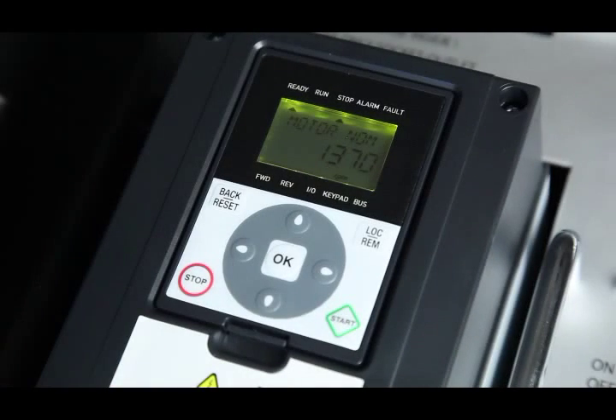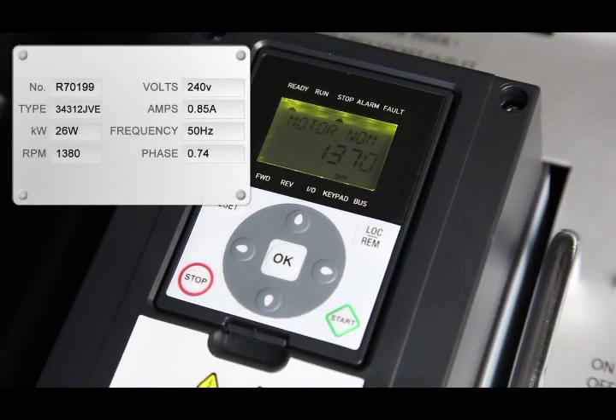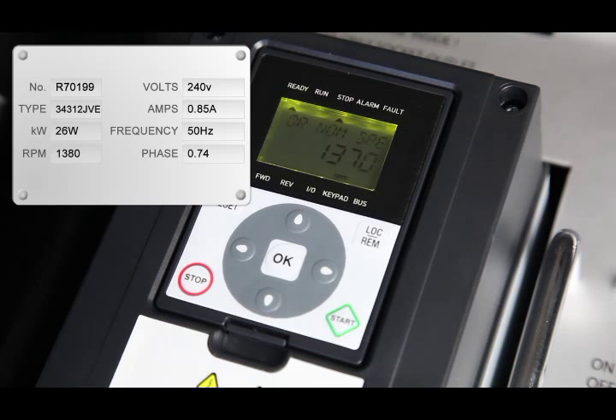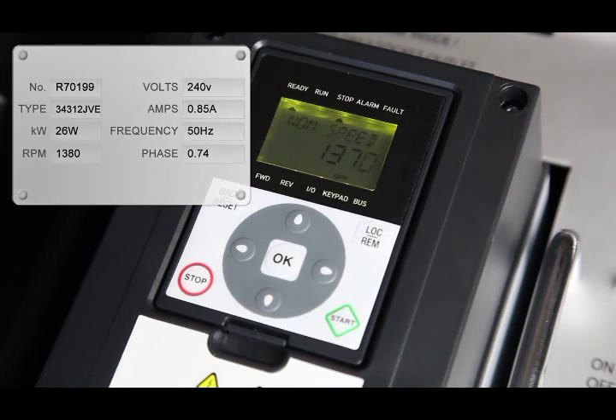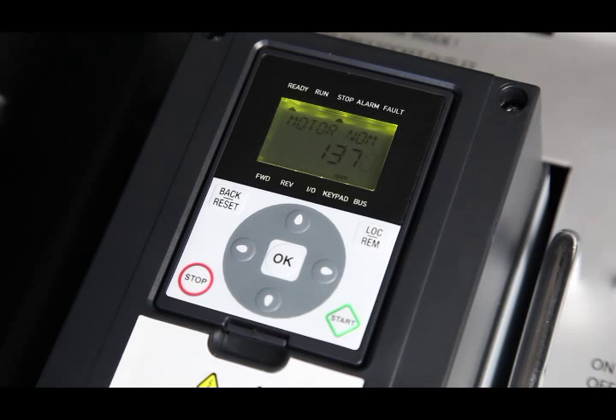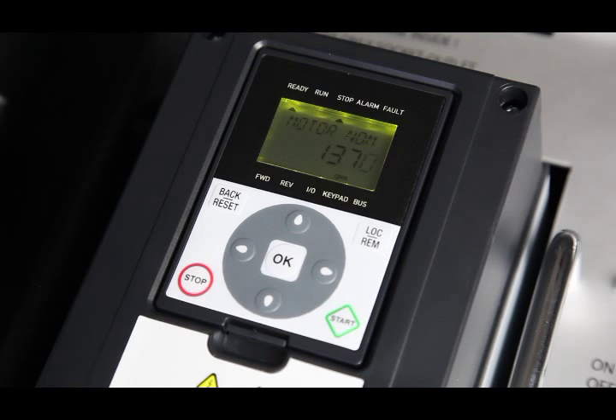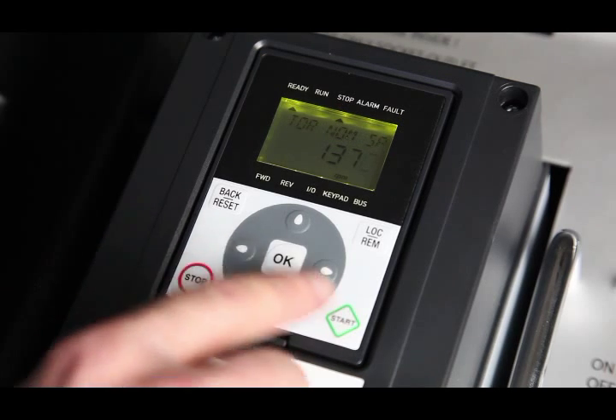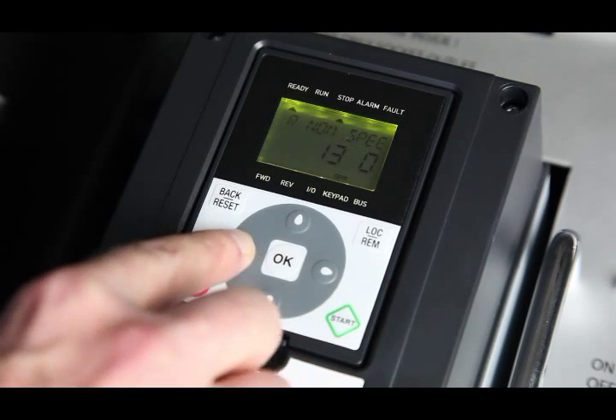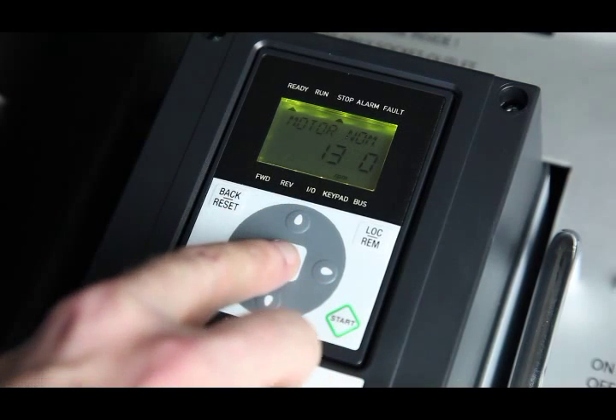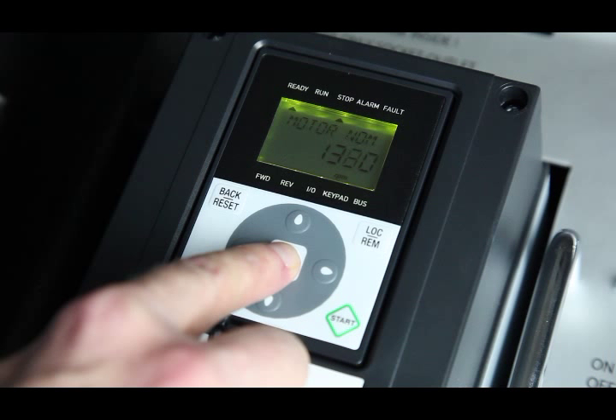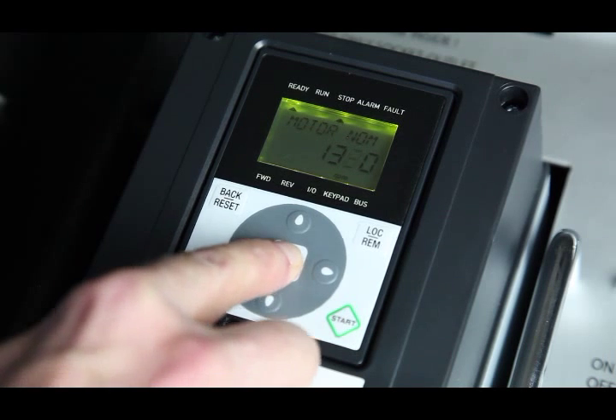It then prompts for motor speed. The data for these parameters can be found on the motor nameplate. The figure that is flashing can be increased or decreased using the up-down cursor keys. Once the correct value is entered, the left-right cursor keys are used to select the next digit. In this example, we will enter 1380 RPM. Once all digits are set correctly, press OK.